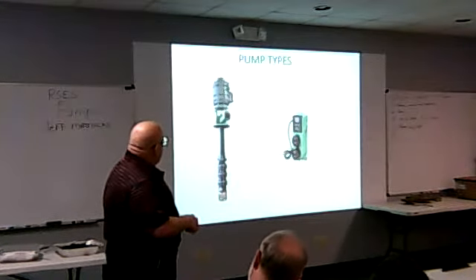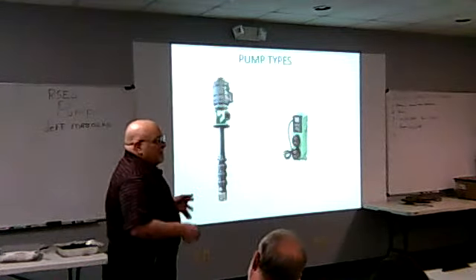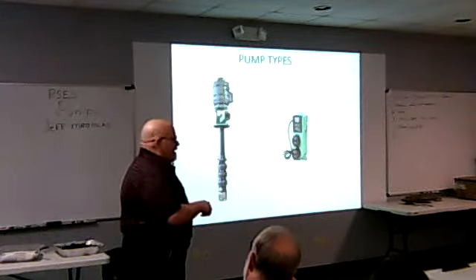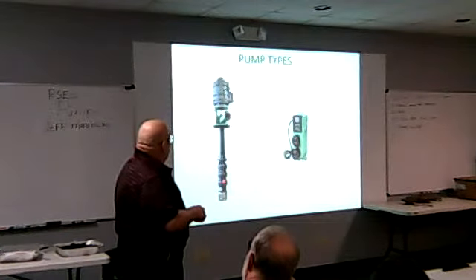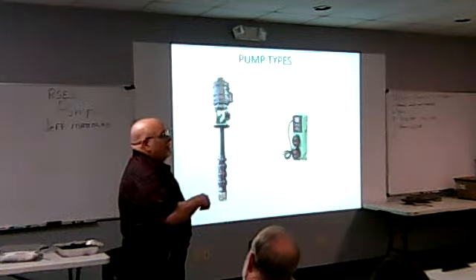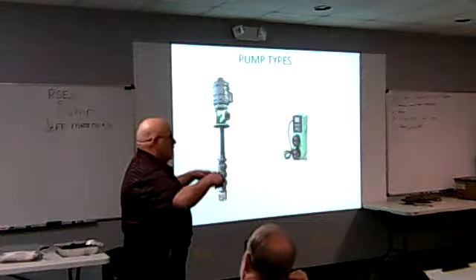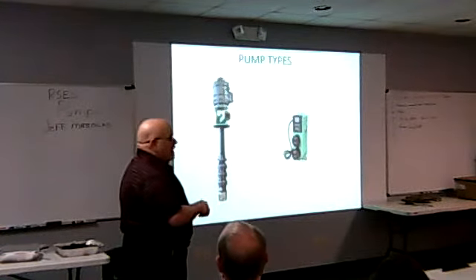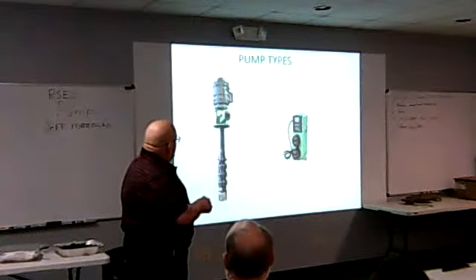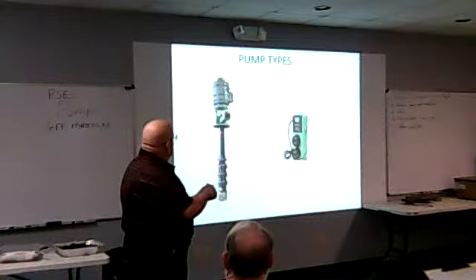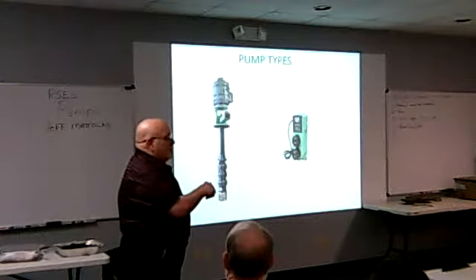There's a strainer here. The more impellers I stack is just like putting pumps in series. I can do 1,000 GPM at 20 feet of head, plus 20 feet of head, plus 20 feet of head, plus 20 feet of head. I go way up in pressure. So it's like pumps in line. And there's just a big shaft here with spider couplings. The impellers sit in here and turn, feed each other. The water comes out and goes out to the system.